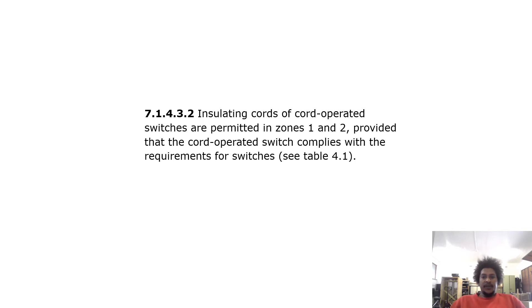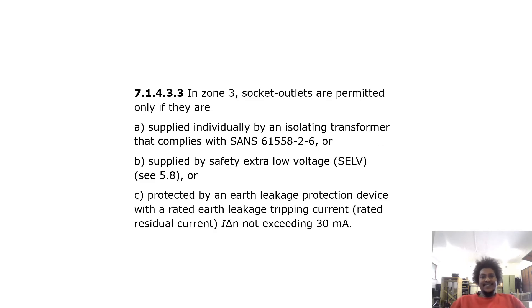In zone 3, socket outlets are permitted only if they are: (a) supplied individually by an isolating transformer that complies with SANS 61558-2-6, or (b) supplied by SELV, or (c) protected by an earth leakage protection device with a rated residual current not exceeding 30 milliamps.